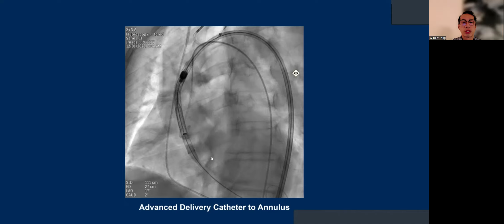The stiff wire placement usually is at the apex, but it's less relevant here with the Navitor platform, because typically we don't even need a third operator or an operator holding the stiff wire maintaining it in place. The left hand holds the catheter in position, for operator one, depending on what your setup is. And then the second operator, or the same operator, can use the right hand to turn the wheel. And you can see how it deploys very easily with even only one person.